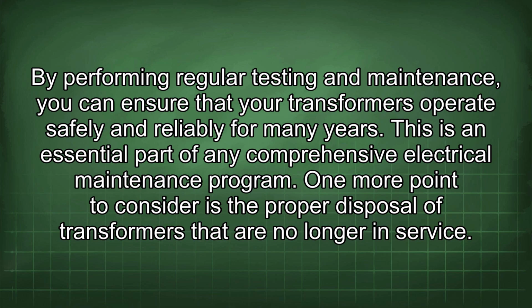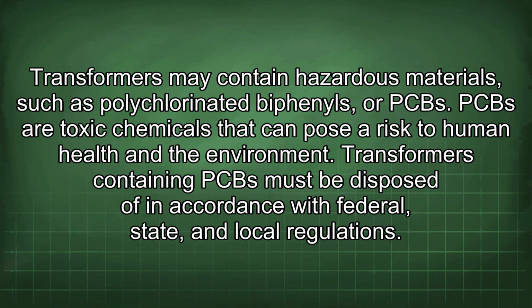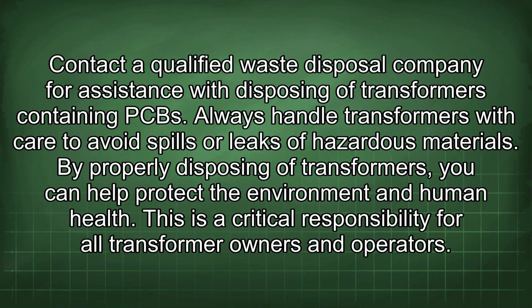One more point to consider is the proper disposal of transformers that are no longer in service. Transformers may contain hazardous materials such as polychlorinated biphenyls, or PCBs. PCBs are toxic chemicals that can pose a risk to human health and the environment. Transformers containing PCBs must be disposed of in accordance with federal, state, and local regulations. Contact a qualified waste disposal company for assistance with disposing of transformers containing PCBs. Always handle transformers with care to avoid spills or leaks of hazardous materials. By properly disposing of transformers, you can help protect the environment and human health. This is a critical responsibility for all transformer owners and operators.